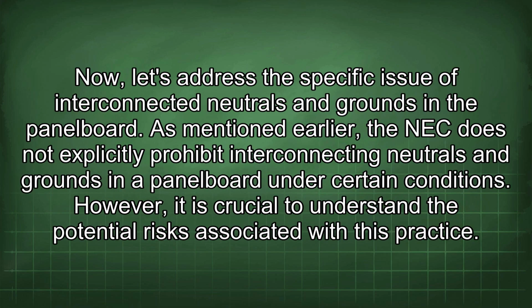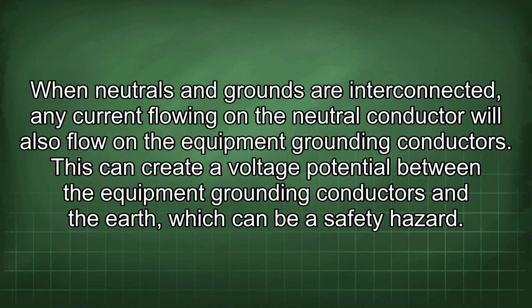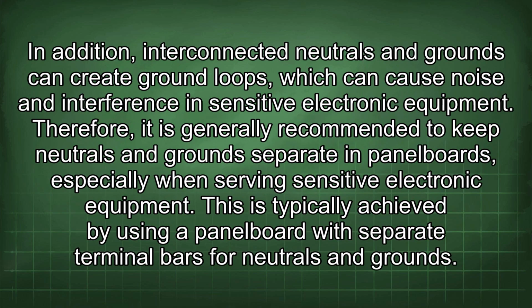Now let's address the specific issue of interconnected neutrals and grounds in the panel board. As mentioned earlier, the NEC does not explicitly prohibit interconnecting neutrals and grounds in a panel board under certain conditions. However, it is crucial to understand the potential risks associated with this practice. When neutrals and grounds are interconnected, any current flowing on the neutral conductor will also flow on the equipment grounding conductors. This can create a voltage potential between the equipment grounding conductors and the earth, which can be a safety hazard.